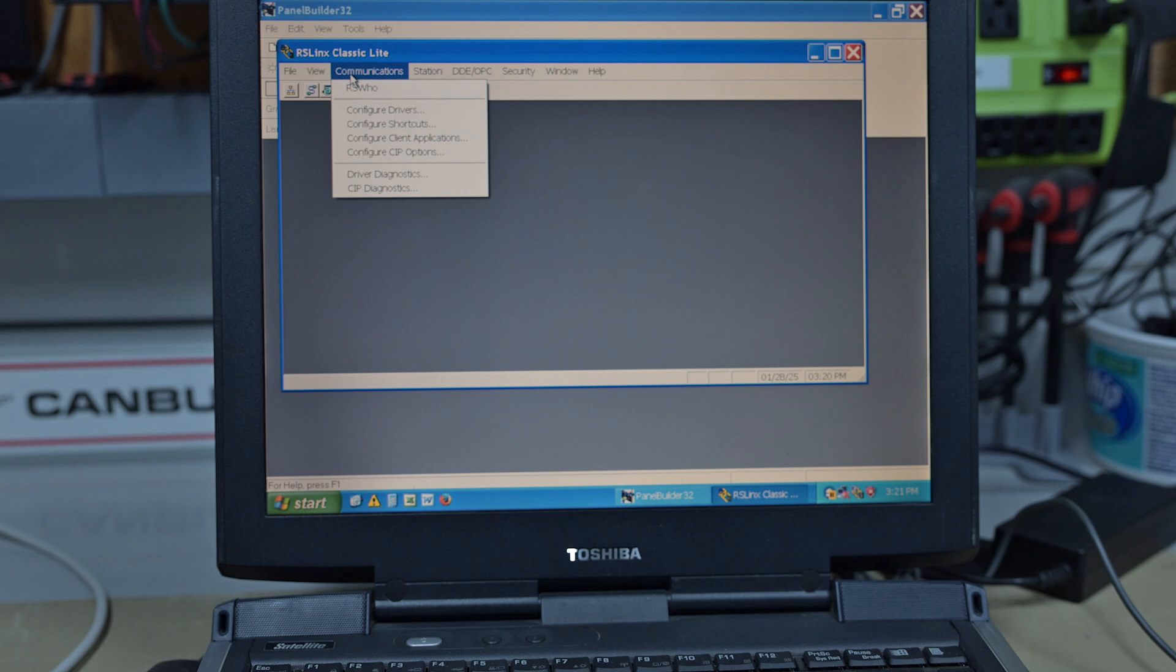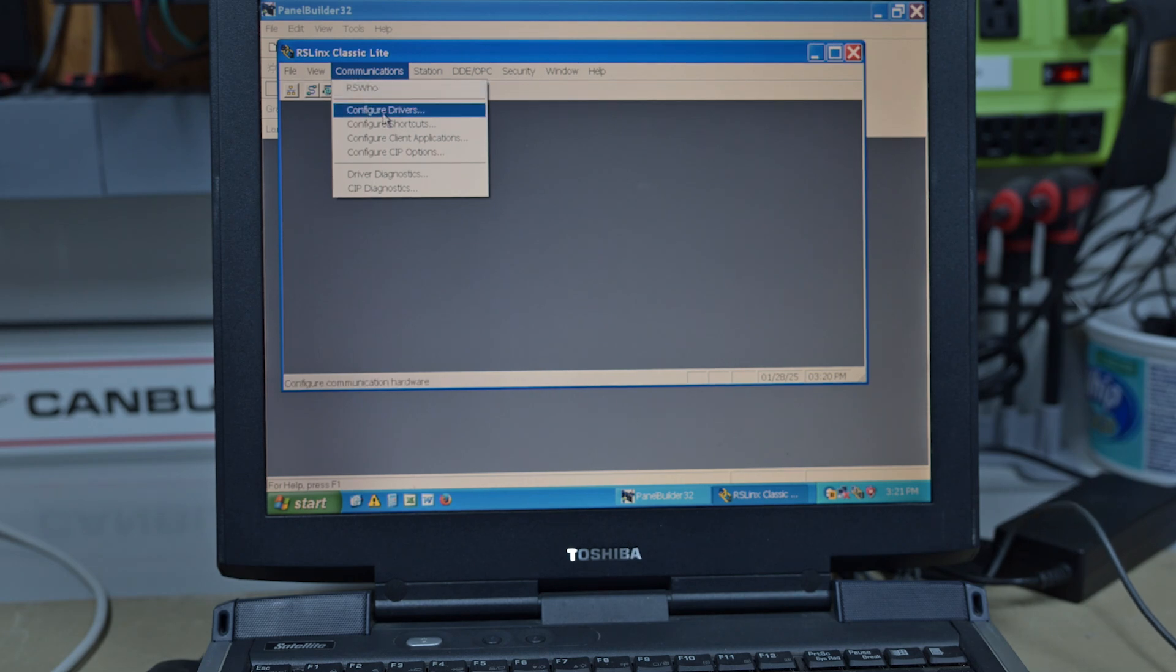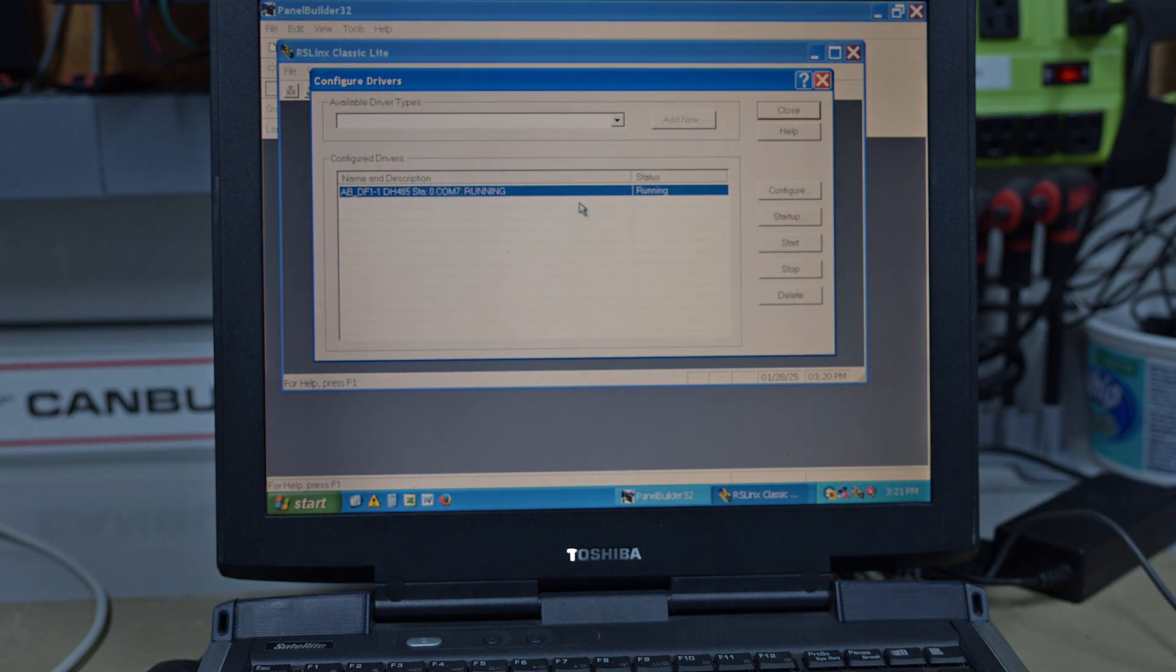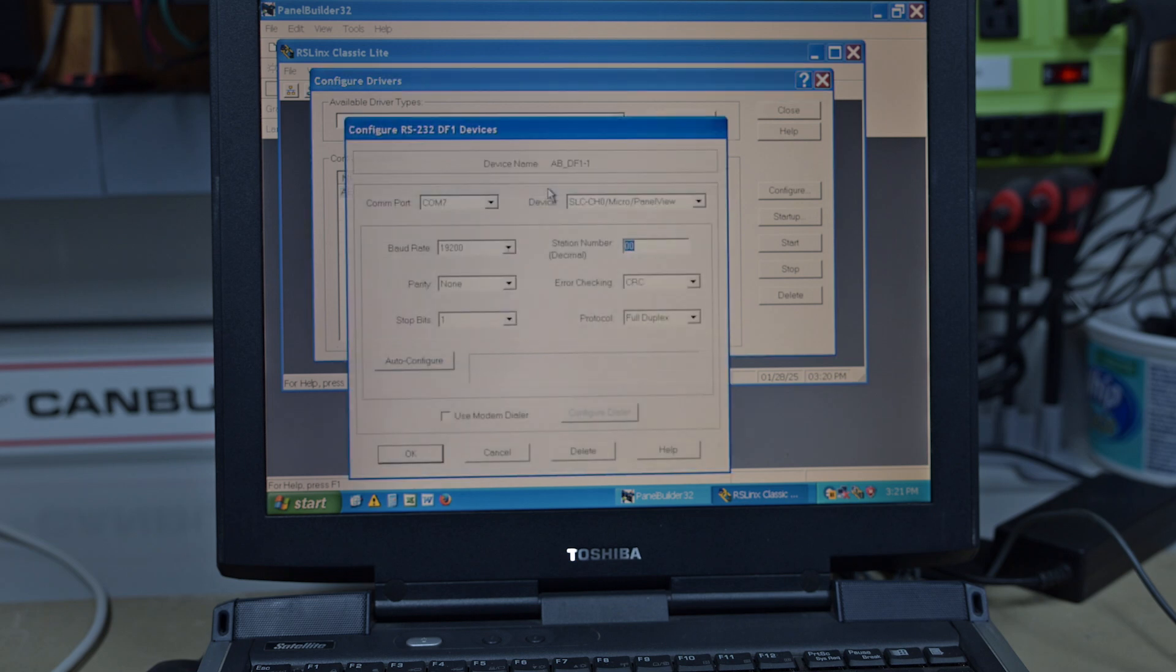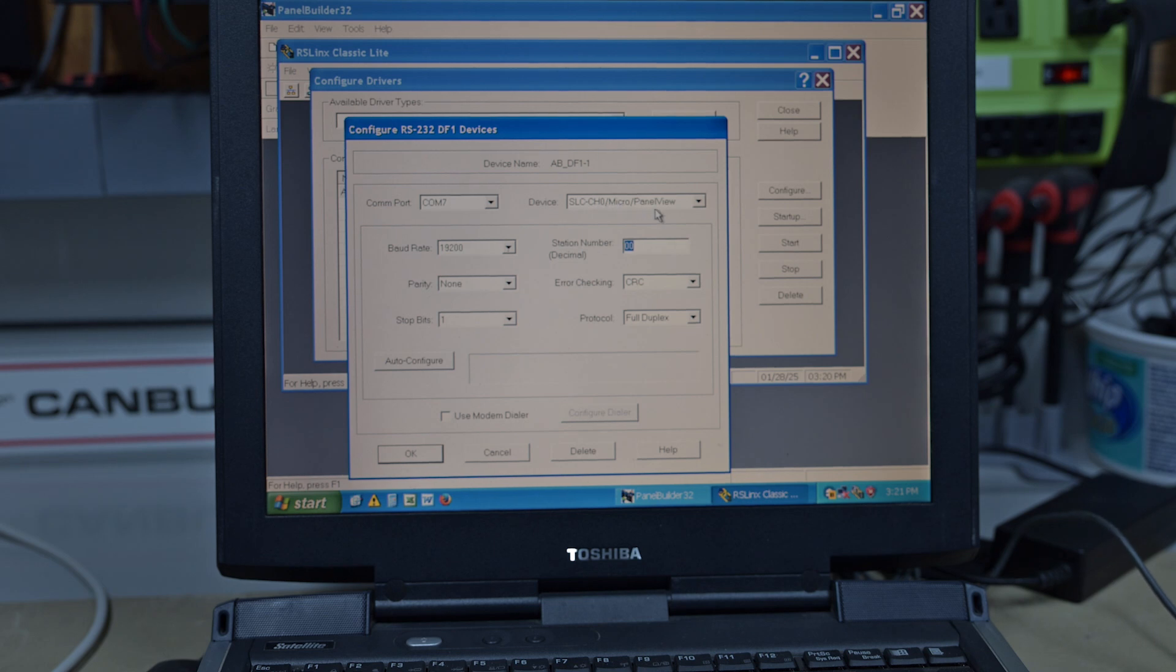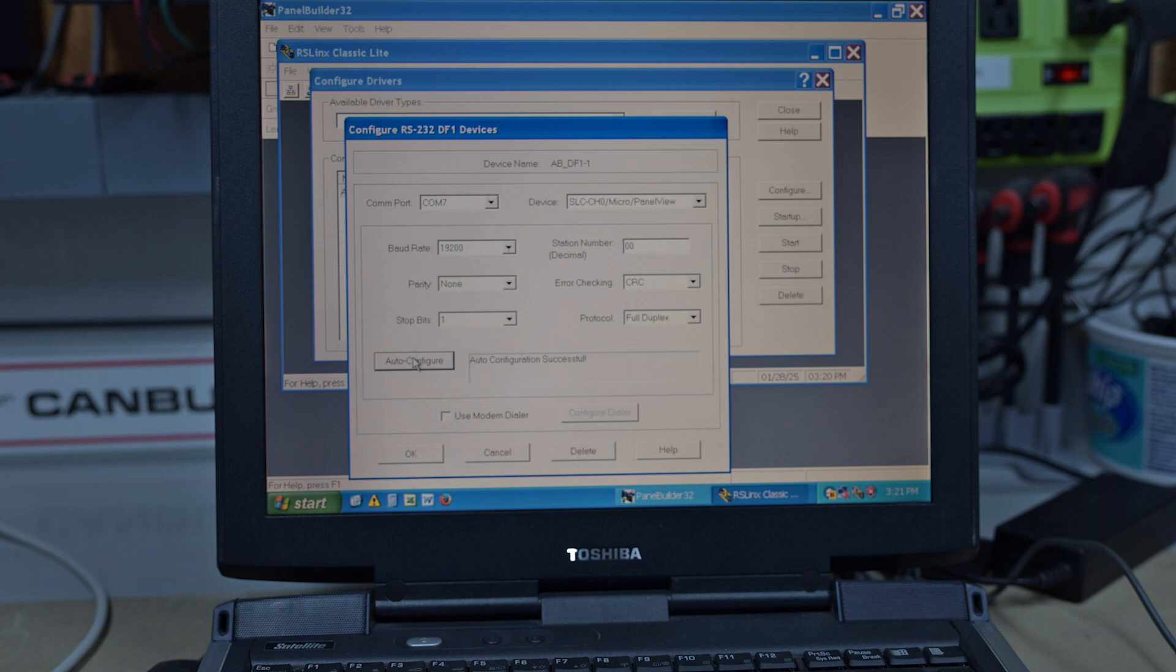Here we are back in the workbench. Let's go have a look at RSLinx. If we go into Configure Drivers and we go into our DF1 which is what we're using, this is set for COM7 going to SLC channel 0 Micro or Panel View. This station number is 0 for the laptop and you hit Auto Configure and it goes through and finds it. It was successful.